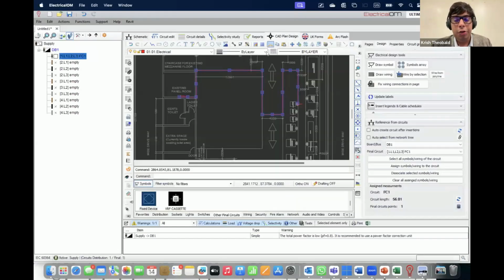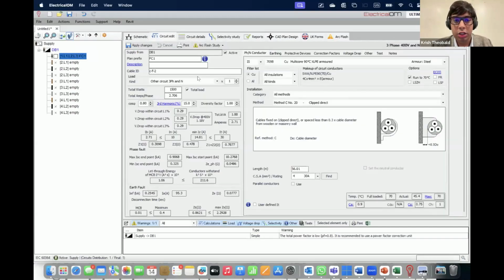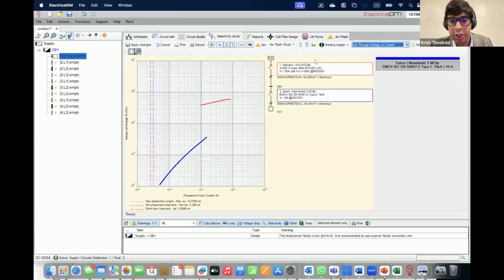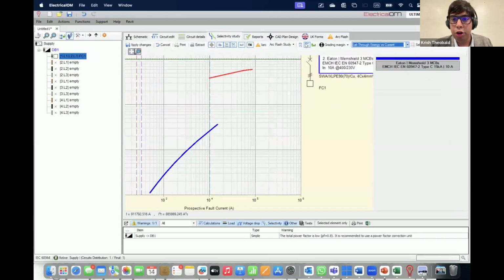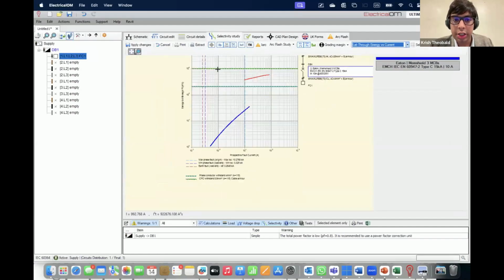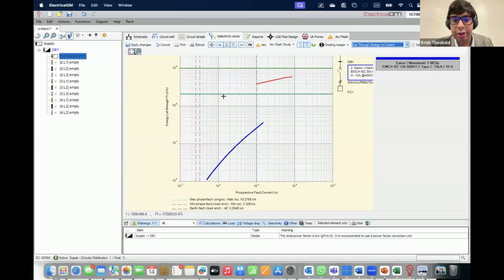Now, obviously, this has done the calculations according to everything. So, for example, what is my fault current at the end point? What is the fault current at the start point? How much let-through energy is there? If you go into our selectivity studies, you can actually see here that for both conductors, this is for our phase conductor, this is for the armor. The device is always allowing lesser let-through energy. So that is your thermal withstand analysis essentially.